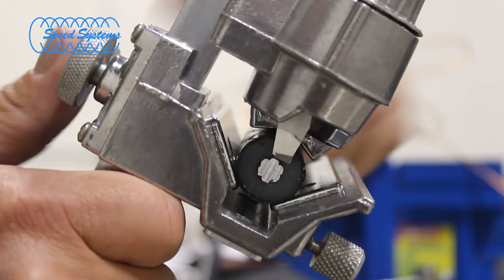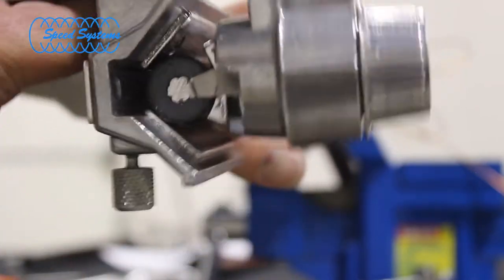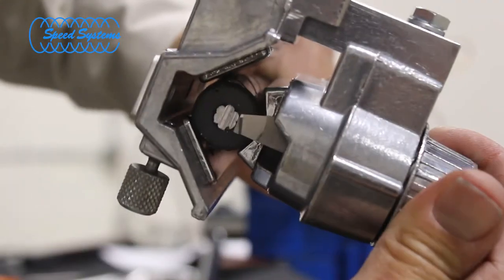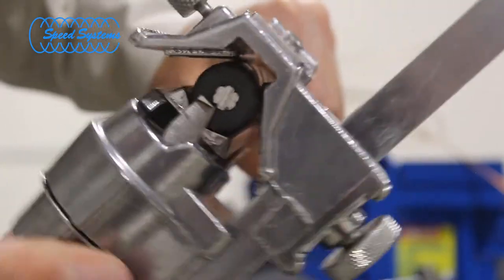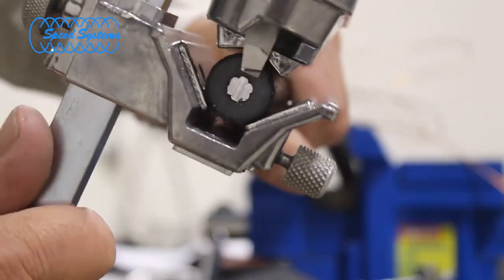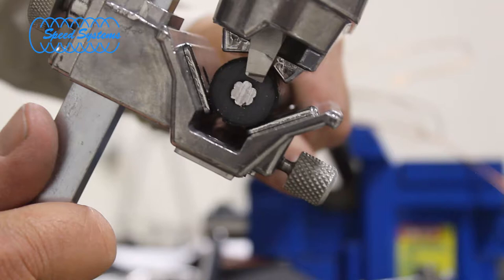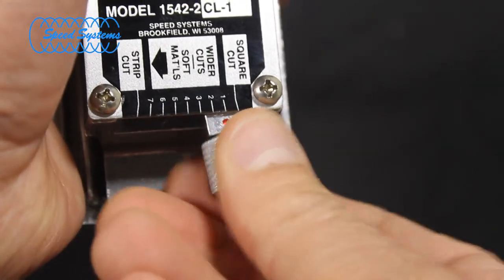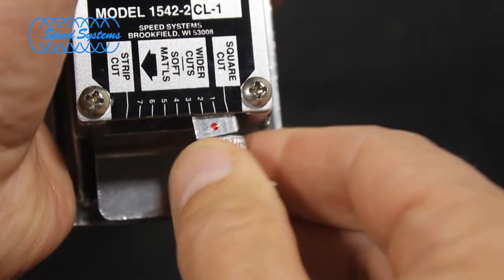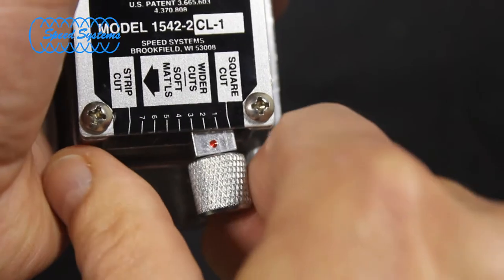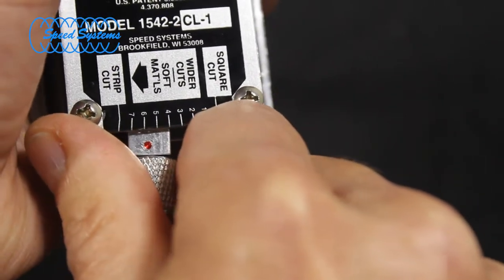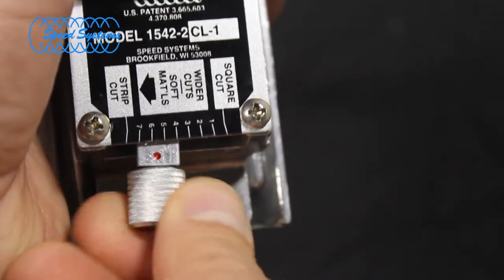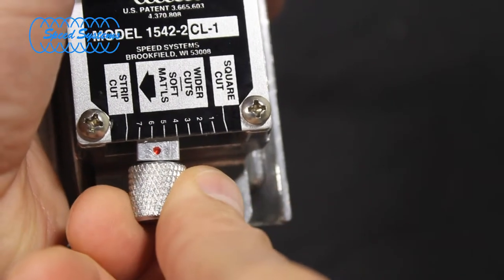Set the blade depth so the blade misses the conductor by approximately 1 sixteenth of an inch. Rotate the tool backwards around the cable before cutting the insulation to ensure that the blade will not hit the conductor at any point. Adjust the blade depth if necessary and recheck. Set the blade cutting angle to the width of spiral you desire. Approximately 1 quarter inch is ideal. As a general rule, harder insulation materials require a smaller spiral than softer materials.